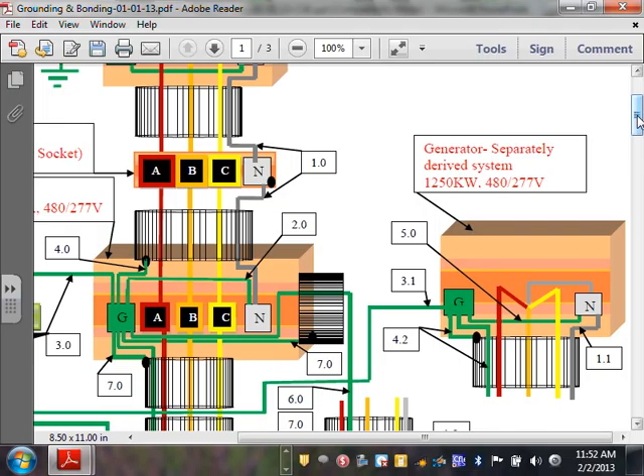Typically inside the transformer it will be sized by the manufacturer and bonded together through copper bars here. But if you were to size it, it will be a wire based on the conductors coming out of the transformer. I have my 3-phase 480 system. I have my neutral coming out. So now I bonded here. Then what do you need to do with your generator? You need to take a grounding electrode conductor, separately derived system, all the way to the steel of your building, or to the grounding electrode bar for the building.